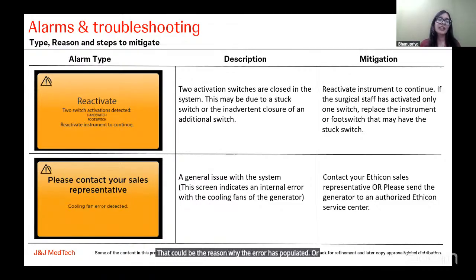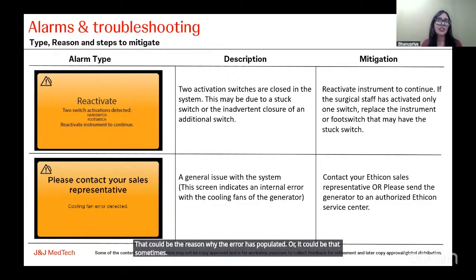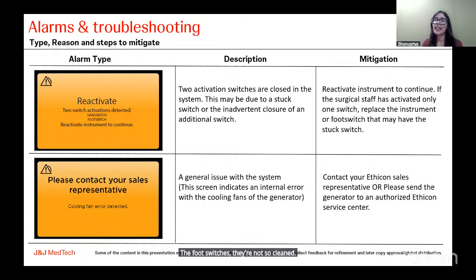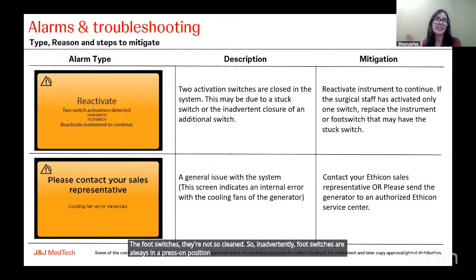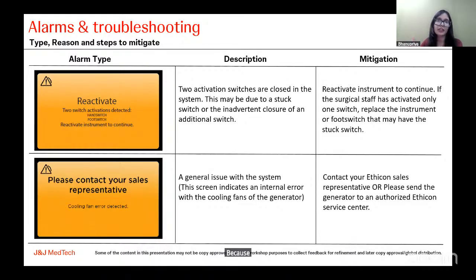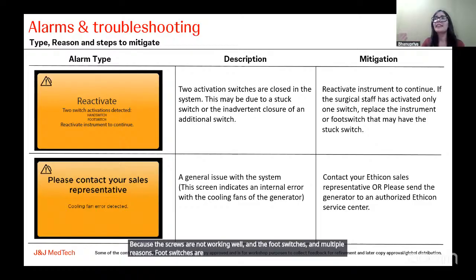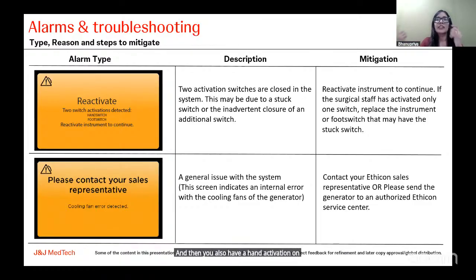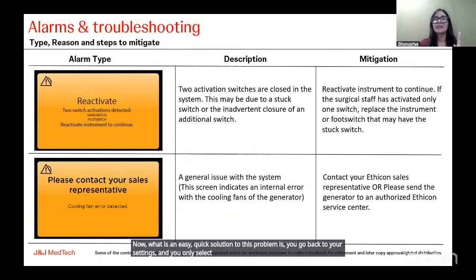Or it could be that sometimes the foot switches are not so clean. So inadvertently, foot switches are always in a pressed-on position. They're already pressed because the screws are not working well in the foot switches, and for multiple other reasons. Foot switches are always on, and then you also have a hand activation on, and that's why the error might get populated. Now, an easy, quick solution to this problem is to go back to your settings and select only single activation, which is the hand switch, and remove the foot switches. A basic way of solving the errors.